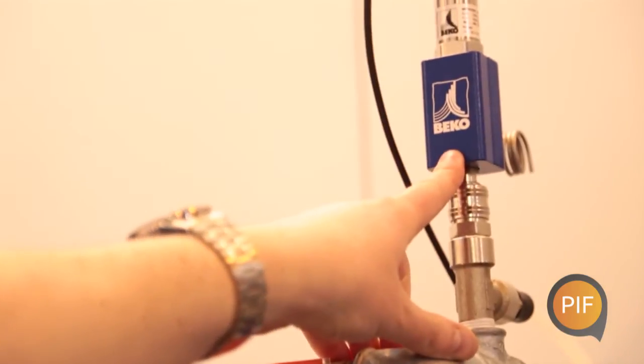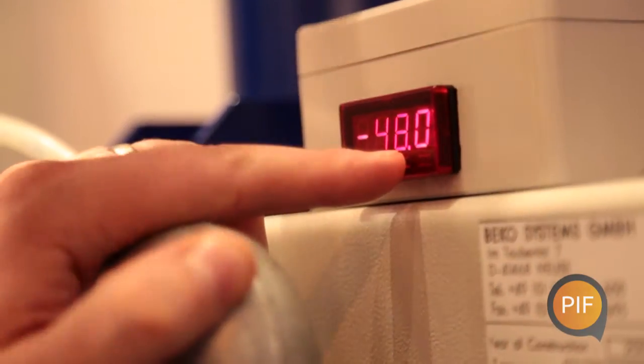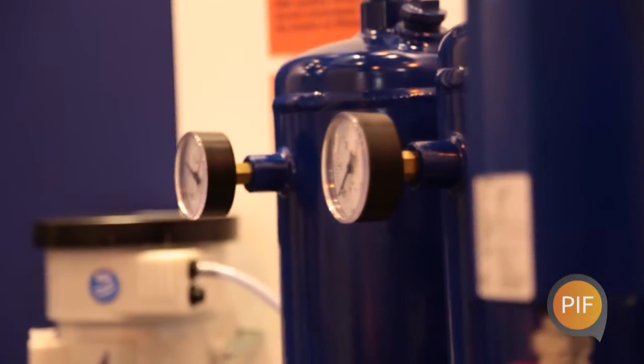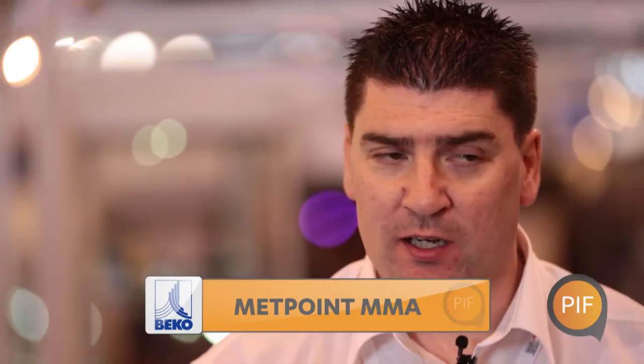Nobody can continuously monitor the oil content like Beko can. Our competitors are sampling the air or doing a quarterly test, whereas we can continuously sample the air. Building on the Metpoint OCV, we're also launching a product called the Metpoint MMA, which in conjunction with oil monitoring, also monitors medical gases — mainly designed for hospitals — including CO, CO2, and all medical gases, continuously online.